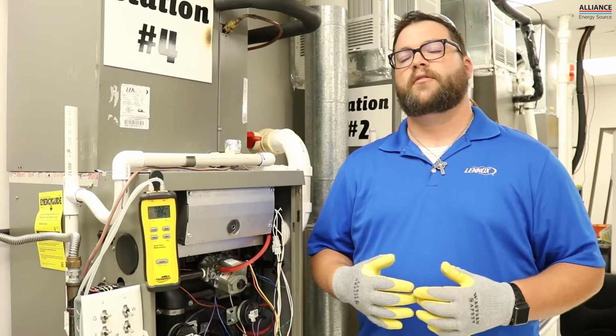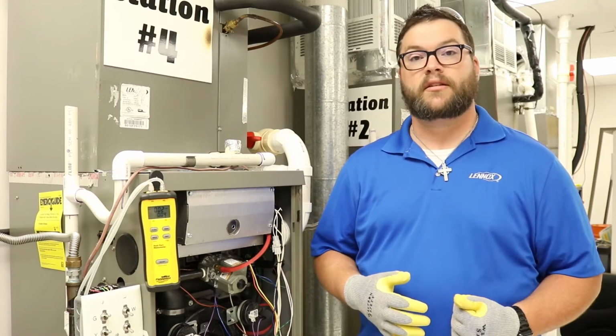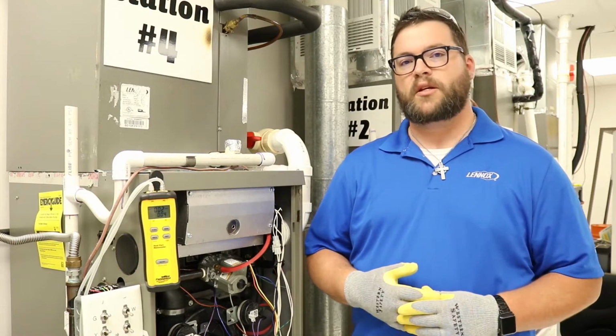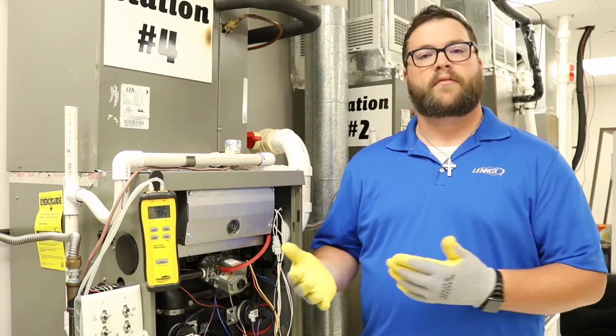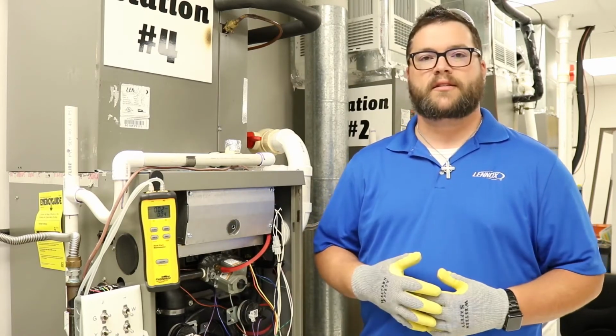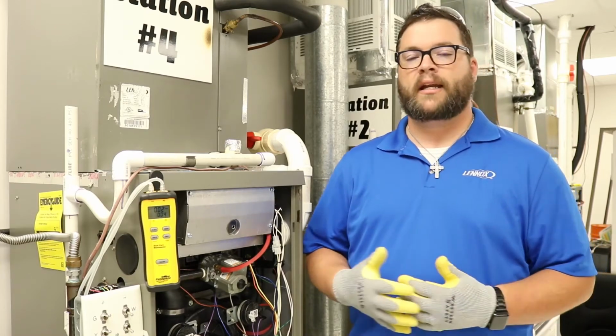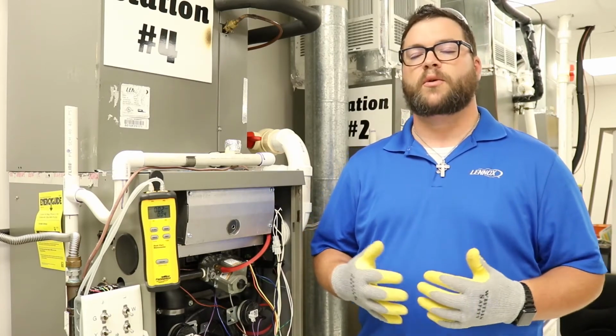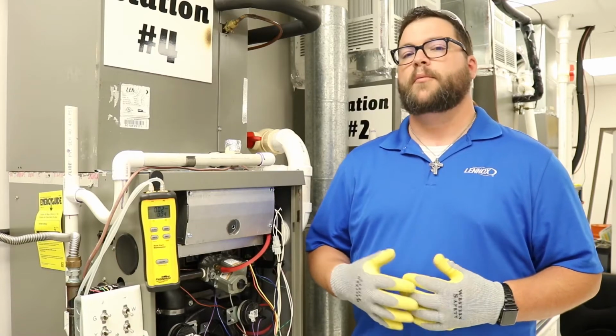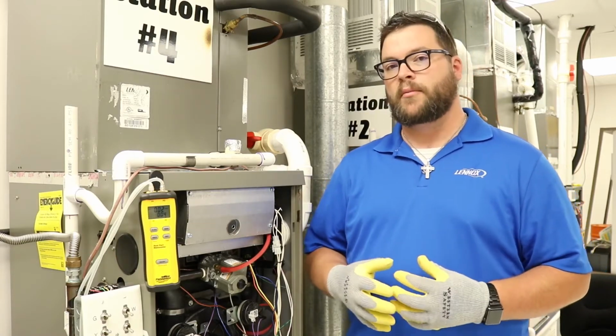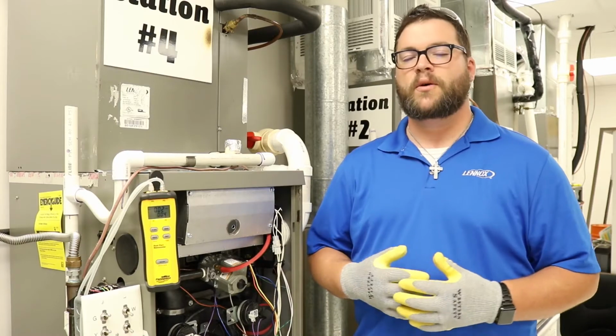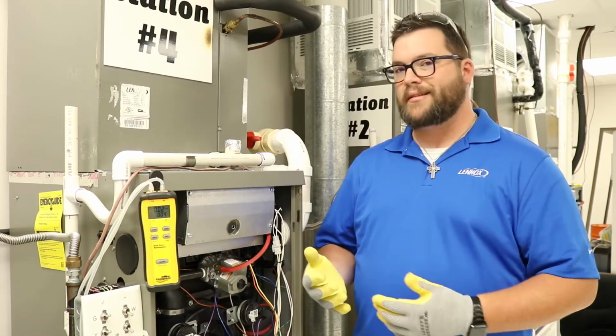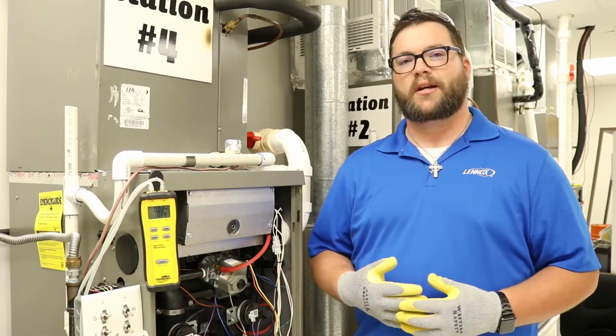Then you find yourself later on down the road putting in a compressor and you're still having the exact same issue again. Could be static pressure or airflow through that system is the main culprit, and a lot of times airflow through the system becomes more of a problem overall than not. So it's really important to understand the basics of checking static pressure, and that's what we're going to cover today.